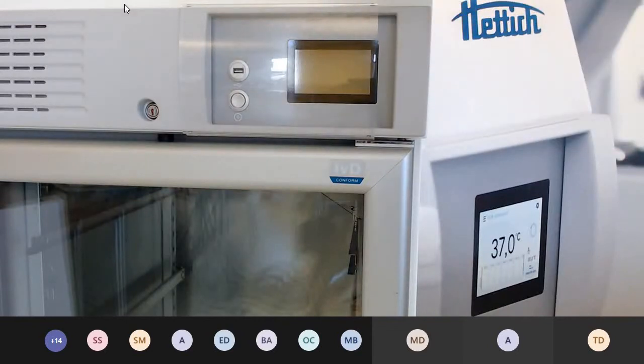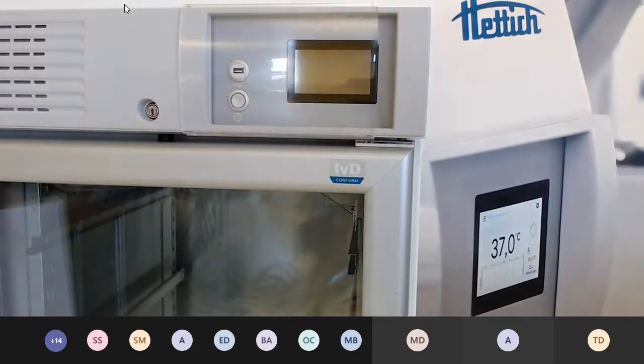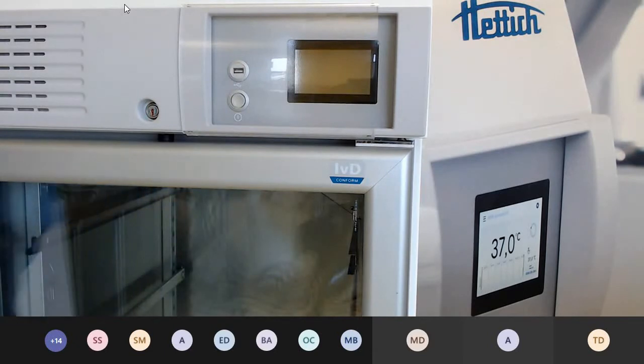We have here a cooling system. That means you can make OQ. We can send you the OQ protocols. You can check the temperature with the external sensors and write it on our protocol down. No, we don't have a reset time. I'm not sure. I will look it up and give you a reply about your question.